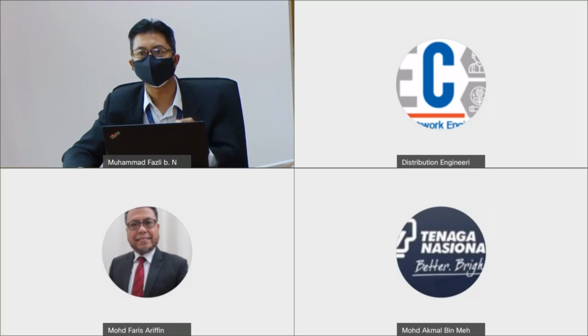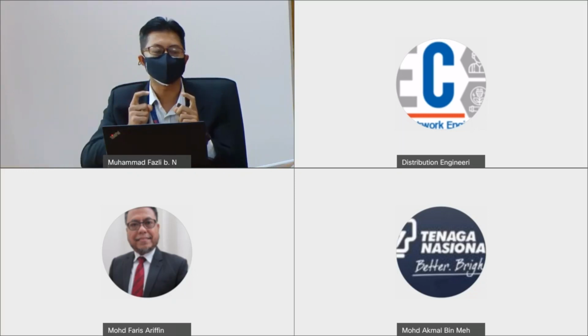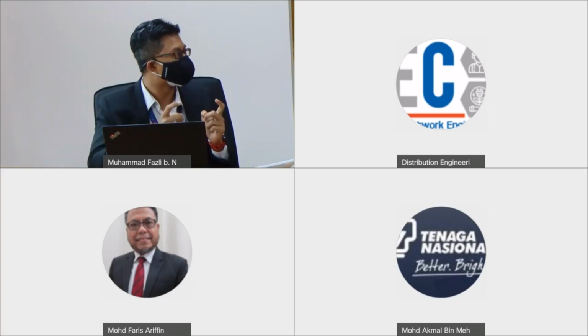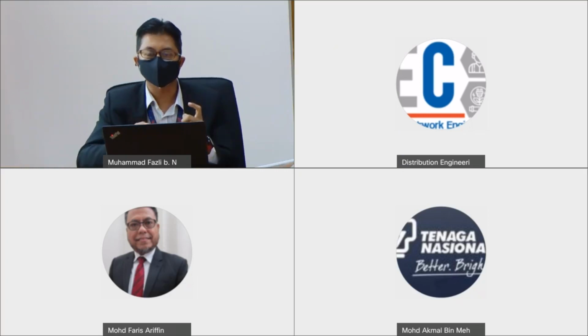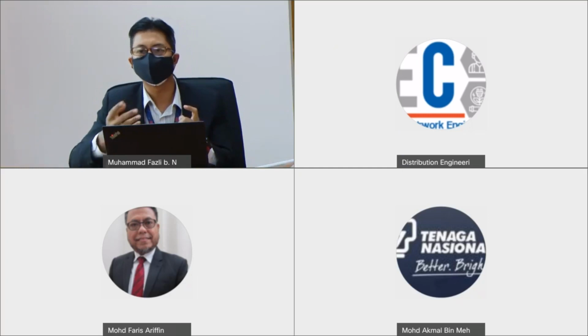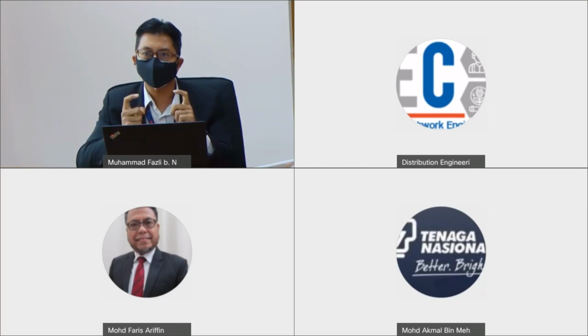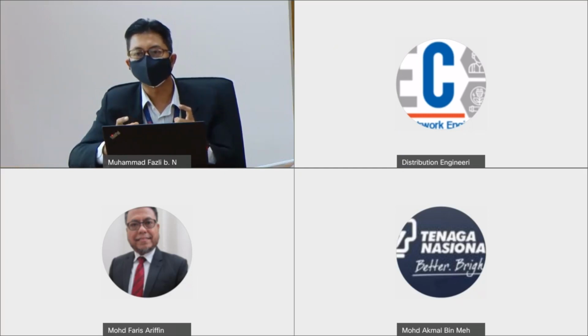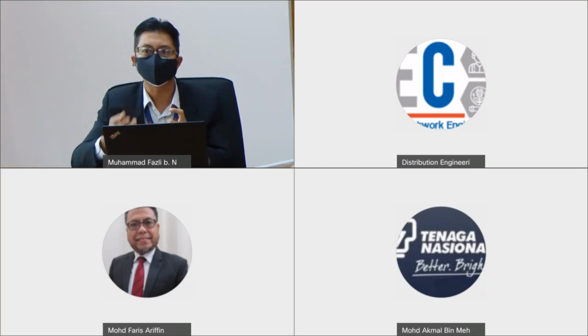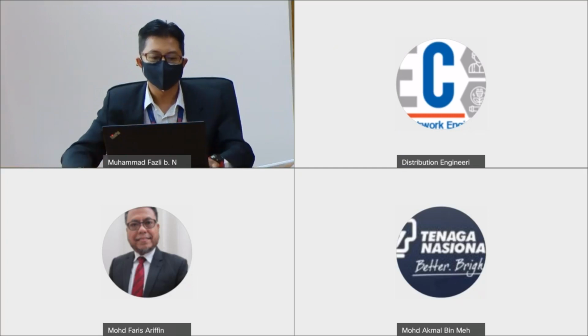And one more thing, you need to take precautions about the maximum gap of the arcing horn, Encik Faris, correct? Yes, so that must be careful, because if you are using a 33 kV system, you must ensure the maximum gap between the arcing horns is 42 cm. Hopefully you can ensure that it is less than 42 cm, because otherwise it can also cause a transient, right?